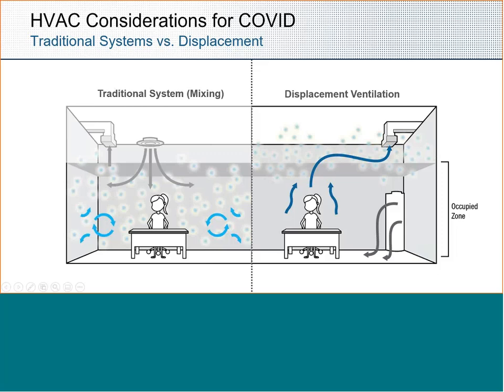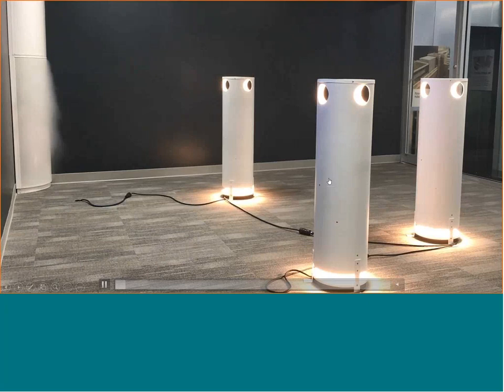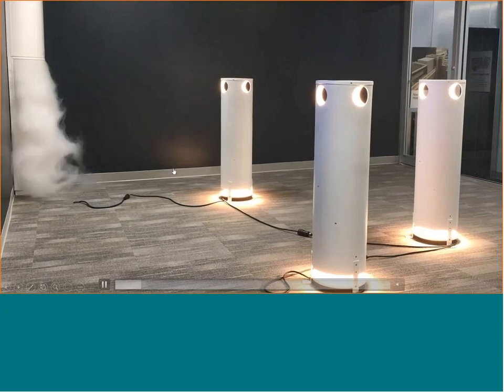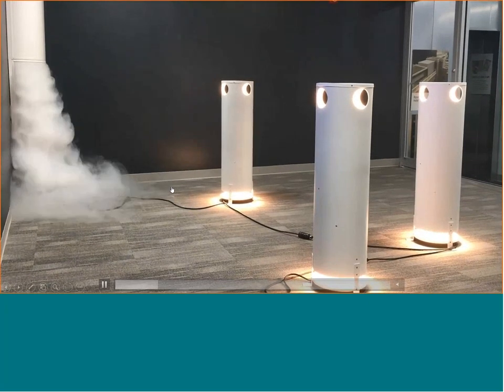But also, throughout the space, especially around the occupied key load, the human load, a lot of that air is moved up across their body because it's all buoyancy driven. So we're pushing a lot of the heat load, but also some of the contaminants, especially the ones that do not fall out of suspension, up and out of the space. What you end up with is a larger concentration of contaminants above the breathing zone, improving the air quality.